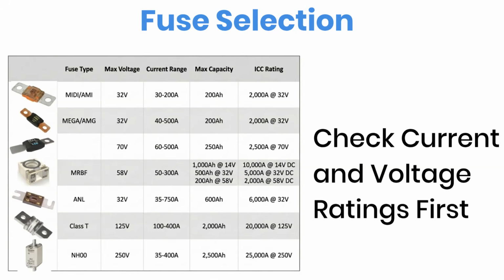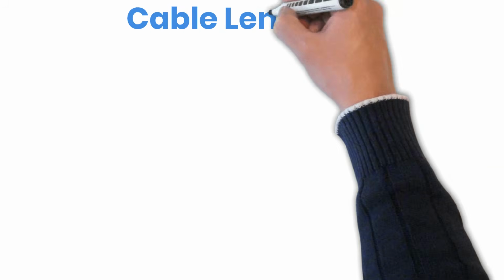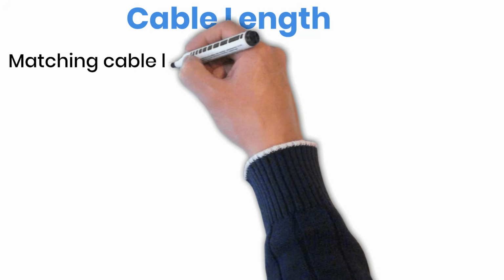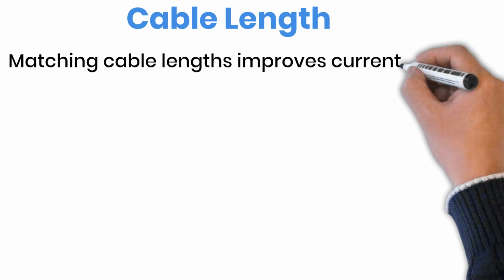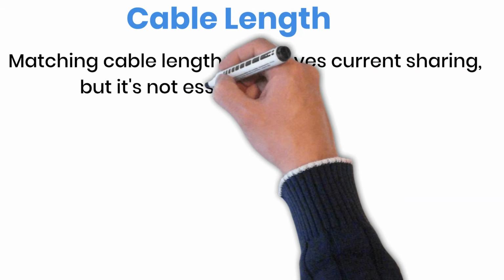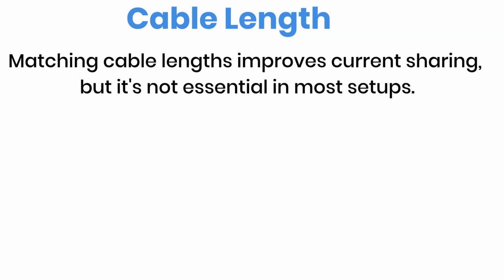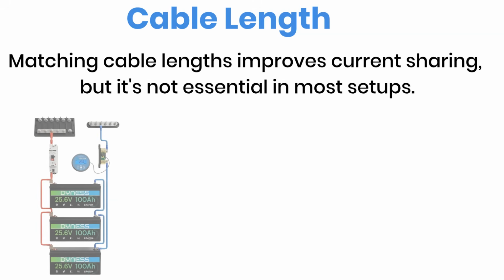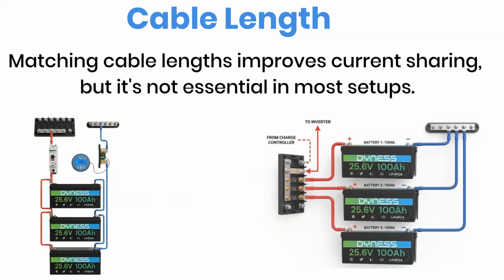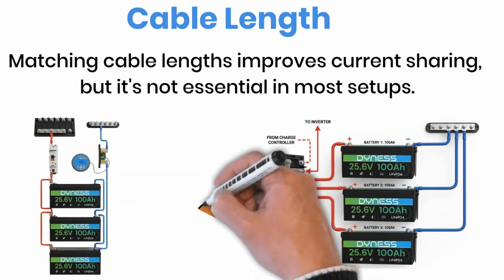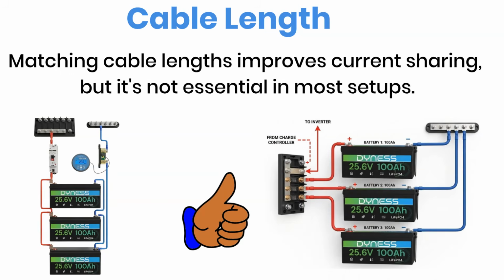Finally, let's clear up one common myth. You've probably heard that every battery cable in a parallel bank has to be exactly the same length. In reality, having similar cable lengths does help the batteries share current more evenly, so it's definitely good practice. But don't get obsessed with making every cable identical down to the last inch. With a properly designed busbar system, small differences in cable length usually have very little impact on real-world performance. Focus on keeping the wiring neat, using the correct cable size, making solid crimp connections, and tightening every terminal to the manufacturer's recommended torque.